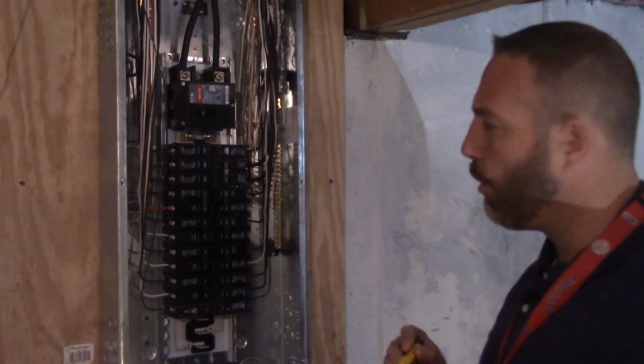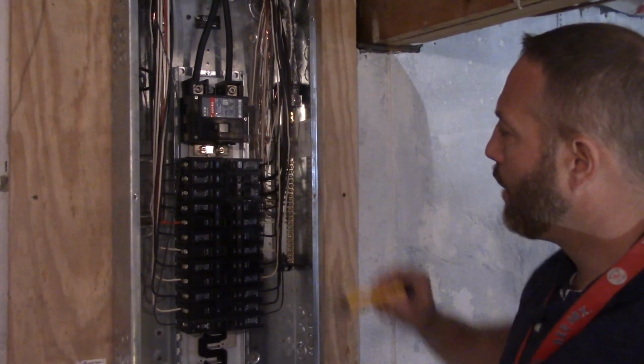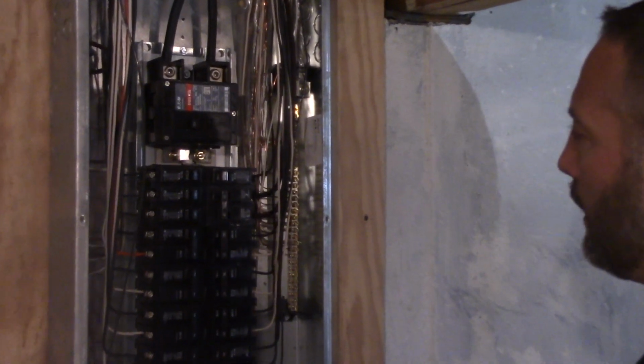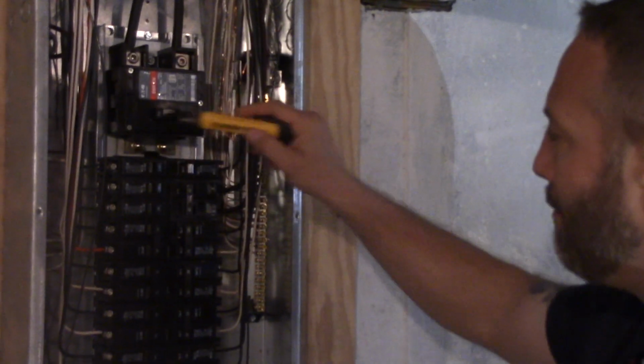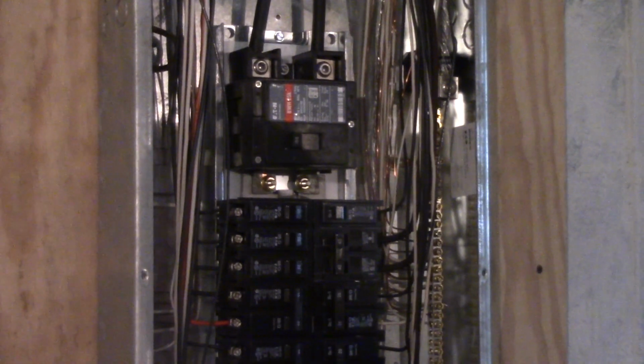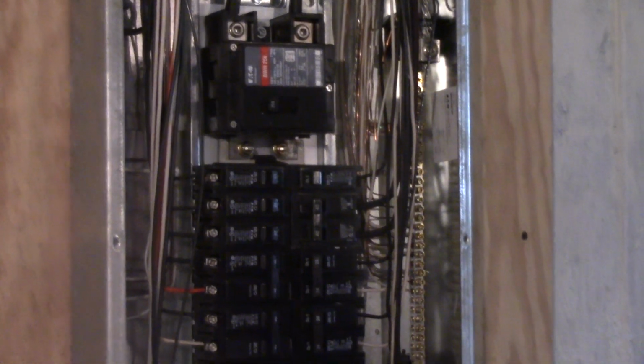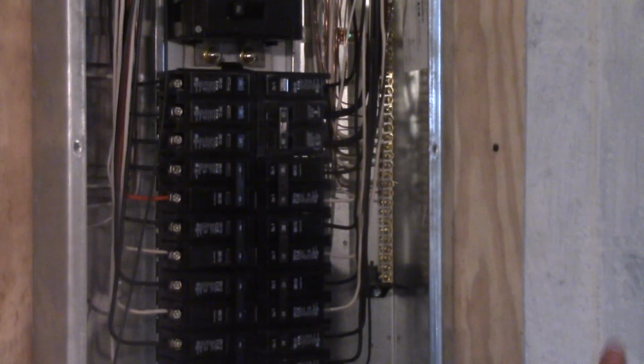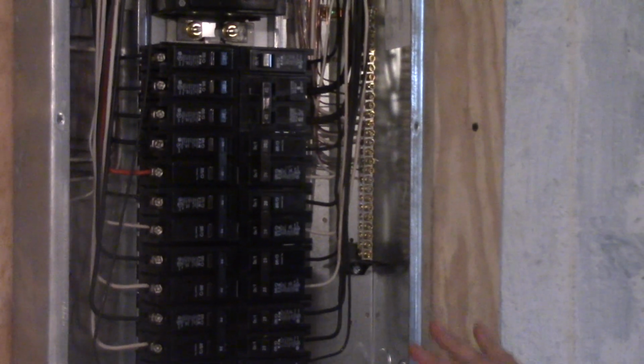Now, to let you know, I never stick my hand in any type of box. I always end up using a voltage tool, just more or less as a pointer. So here, our main electrical breaker is 150, and it's by itself. On some systems, it could be among the breakers on the older systems. So we're going to mark that down. The type of protection. Typically, we have circuit breakers. You can see fuses. We don't have any here.